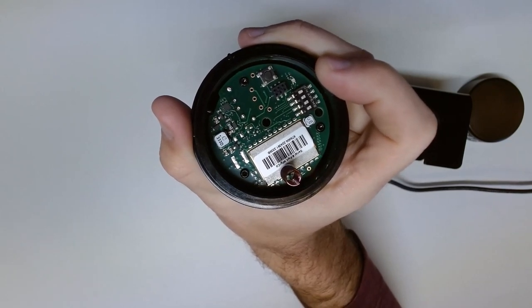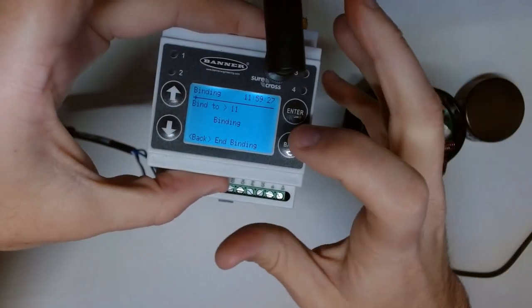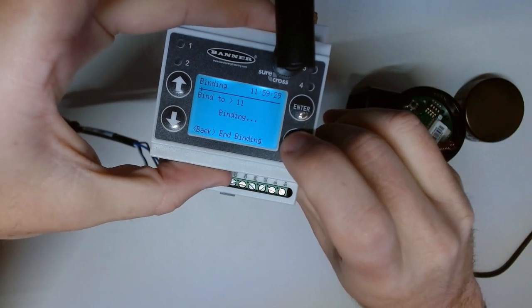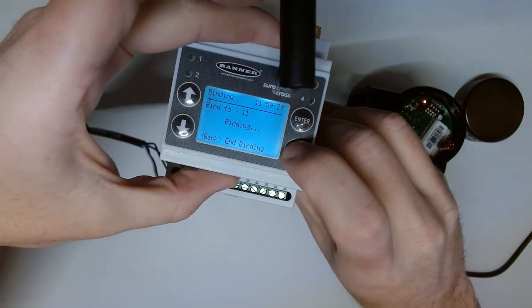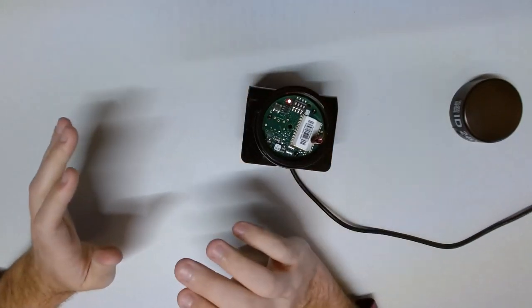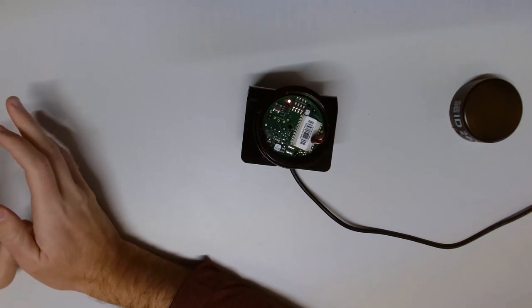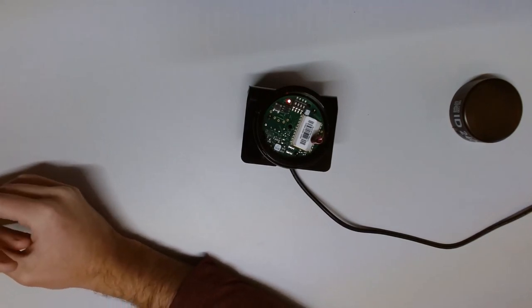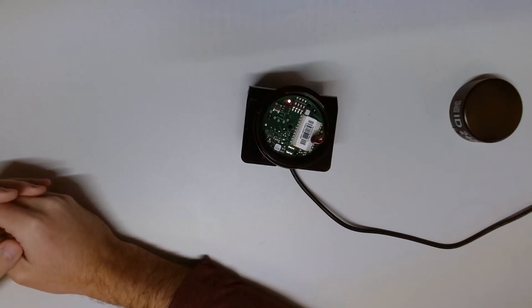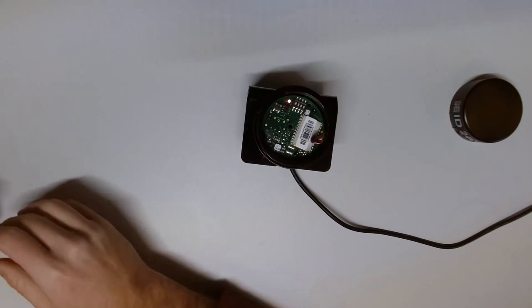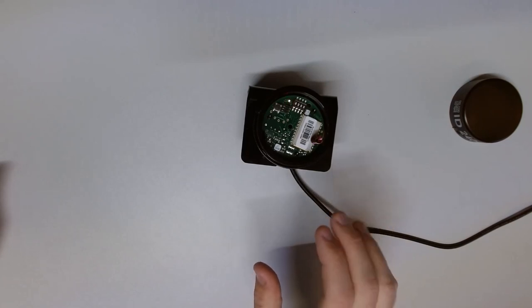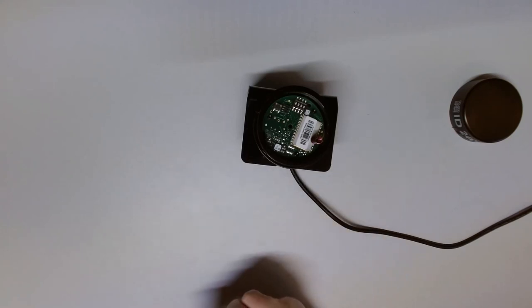As soon as that is done, I can then hit the back button to get out of binding mode on the DXM. And until I do that, the devices that you may have bound in wouldn't start trying to form into the network as this one is doing now. So, if you wanted to go on to the next one, you would hit back, you would increase that number to 12, click binding to enter binding for that device.